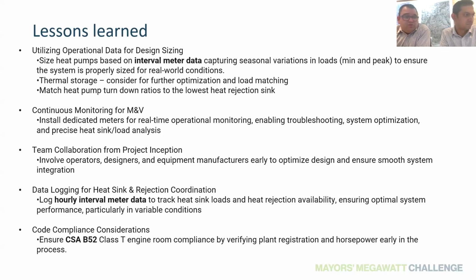And yes, continuous monitoring and measurement and verification is needed: install dedicated meters for real-time operating monitoring, troubleshooting and system optimization. It's really helpful at the stage where we are, when we're trying to optimize the system and the run hours. You need data. You need to see the temperatures in and out. You need to see the flows. You need to see the run hours of the equipment, so you can create the profiles and provide sequences of operation for summer, spring and winter operation, as those are actually different. And if you want to really have an optimized system, not that it cannot operate without them.